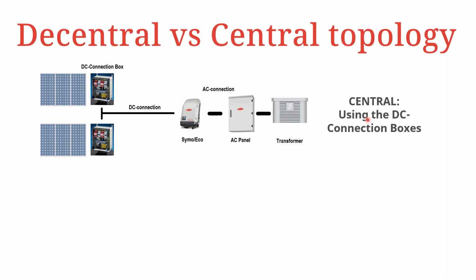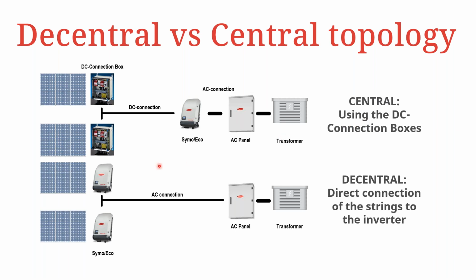AC combiner box. In contrast, you can also achieve a decentralized topology whereby the PV power from the PV array, each string, is connected directly to the PV inverter. So depending on the Symo, you can connect 3 strings per MPPT, and with the Eco, you can connect all 6 strings directly to the 1 MPPT. In this case, AC power is traveling a much longer distance than DC power, and therefore thicker AC cabling is required for connection.